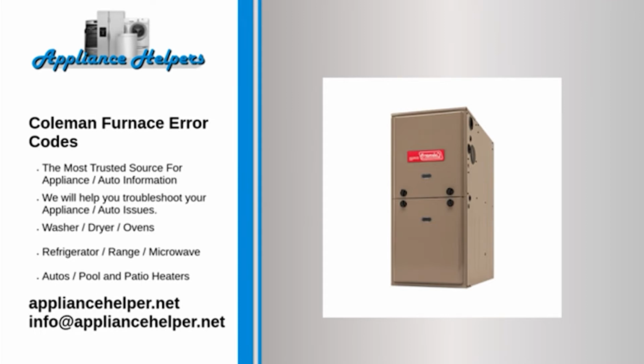Code: 9 red flashes. Problem: there's a grounding or line polarity issue. Fix: check the polarity at both the furnace and branch. Code: 10 red flashes. Problem: gas continues to flow with no call for heating. Fix: check on the gas valve and the gas valve wiring.